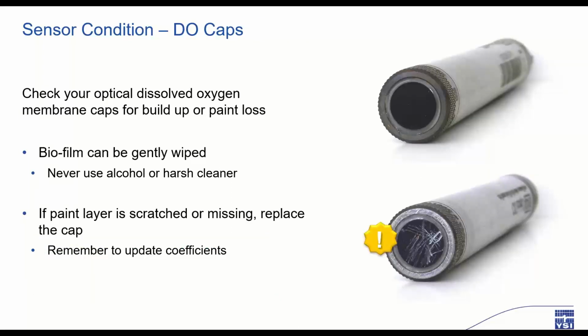After we're sure that the DO membrane cap was indeed stored moist, we also need to inspect the membrane for film, buildup, or scratched or missing paint. If there is biofilm, usually a gentle wipe with a moist Kimwipe will be enough to clean off the surface of the membrane. Never use alcohol or any other harsh cleaners on the face of the membrane, as this will damage the paint.